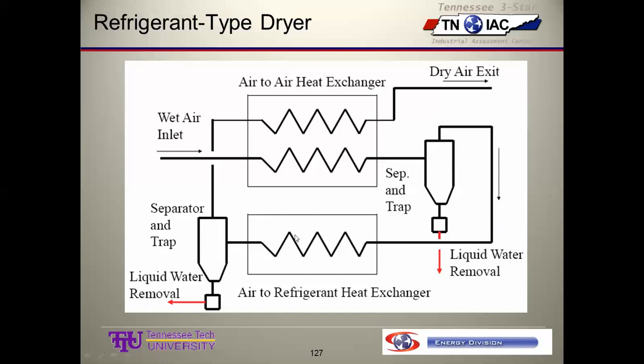As we cool it down, and this doesn't show the refrigeration system, which I'll show in the next couple of slides, it cools down to, like I said, nominally 35 to 38 here, and we wring out a lot of moisture here. So we drain some from this, and then we put it through a separator, pull out any drips, droplets, whatever, probably a cyclone type device. So we see liquid water removal down here. This is the cold air that's dry, but it's at saturation at the low temperature. We preheat it, and it goes out to the system.